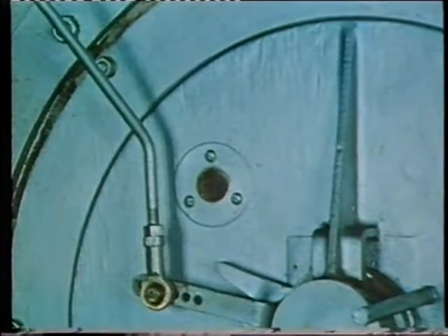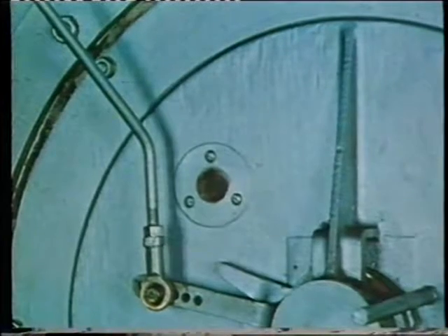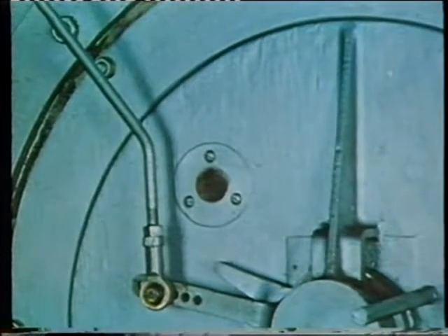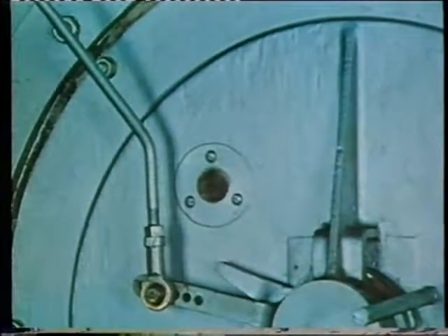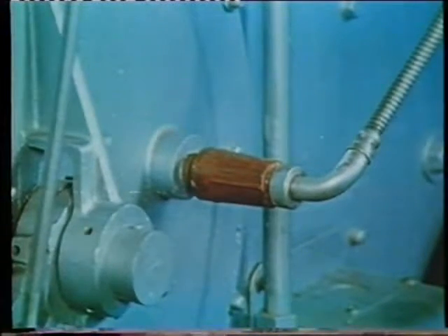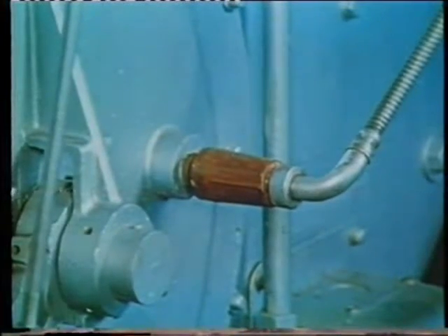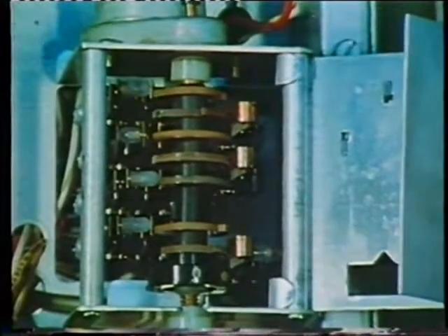When the pilot flame is proven, fuel is directed into the burner and ignited. The flame viewing window permits the fireman to observe the flame. The scanner now monitors the main flame and shuts down the fuel valve in the event of a flameout. When main flame occurs, the ignition sequence is complete and the program timer halts at the run position.